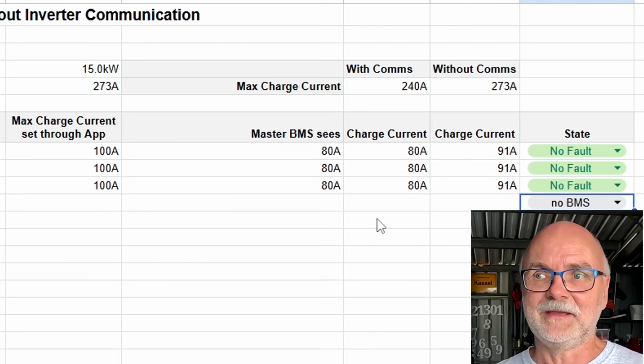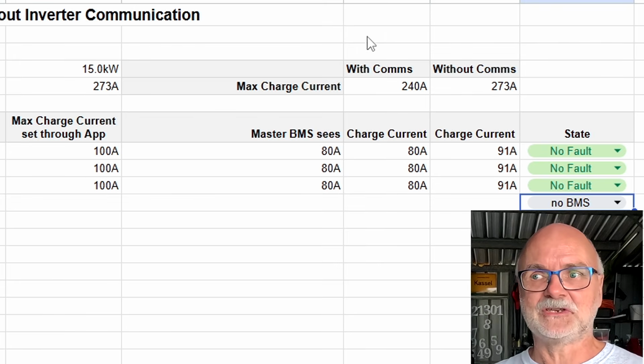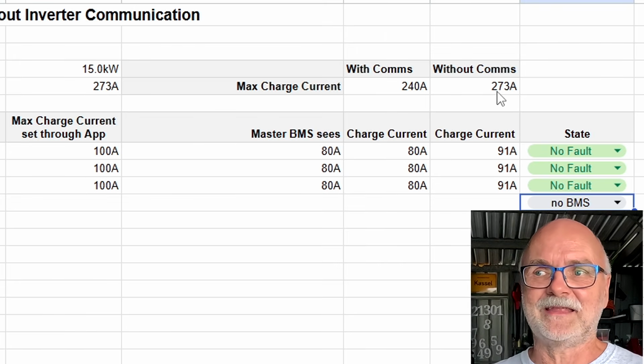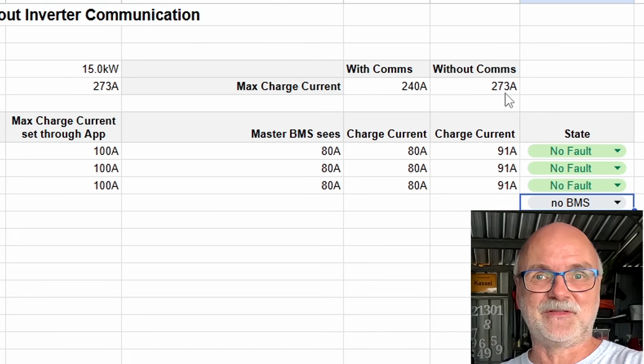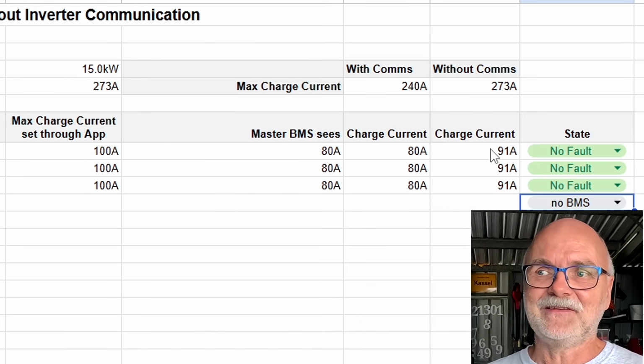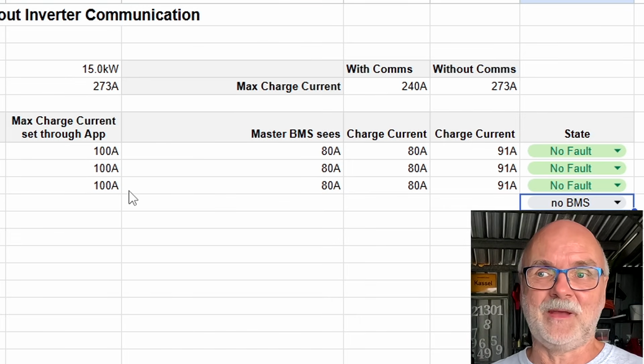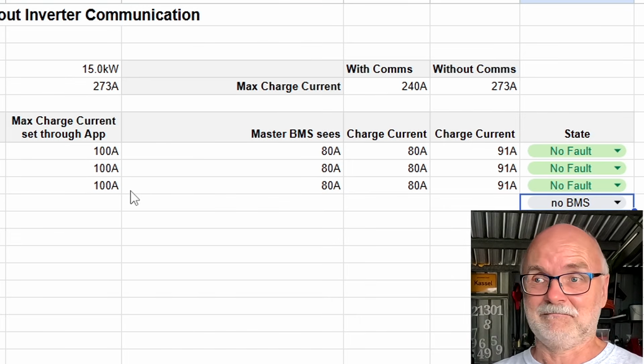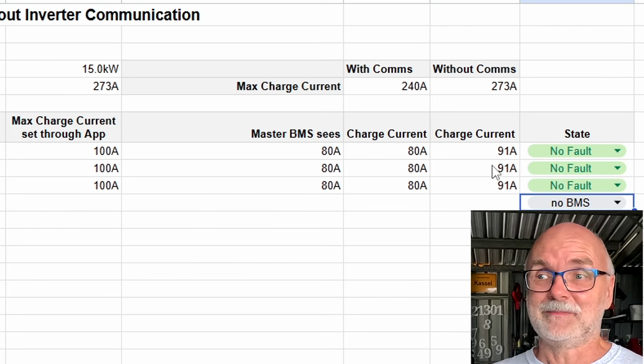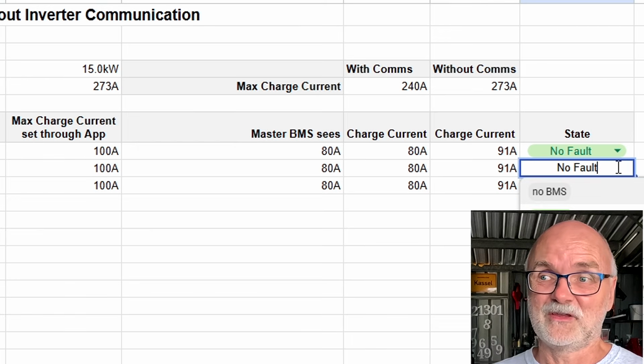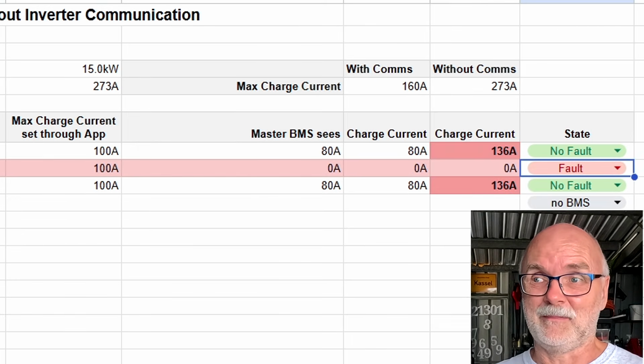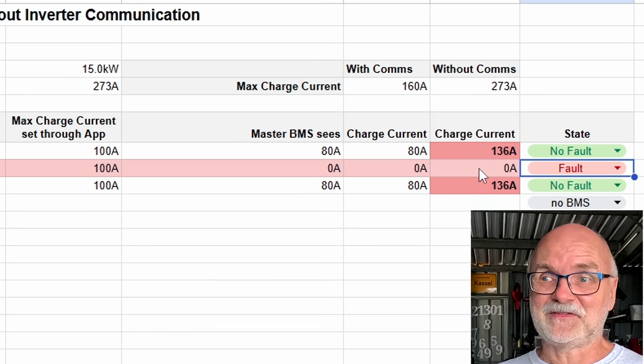What happened to me? And I have no communication. So I'm charging with 273 amps into the system here. 91 amps into each of the batteries. Still okay. We are under 100 amps. But now one of the batteries goes into a fault because the middle shelf battery has this over temperature protection now. Bam. Yeah. And you can see what happens now.